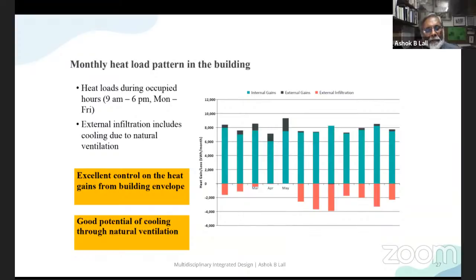And when you're reaching a broadish configuration of the building, our simulation man steps in and says, okay, now, you know what? I'm just going to tell you what's happening to the building in the whole year. And he says that, look, if you can make use of all the natural ventilation that Swati is promising, if you get it right, if you can make use of the evaporative cooling potential by using cooled water by evaporative cooling to take away the heat from your building, if you can do these two things, and if you can then shade the building from the impact of direct sunshine as much as possible, and you can insulate it sufficiently on the roof and on the walls, then you can expect that the overall energy consumption in the year will be so much, gives a number.